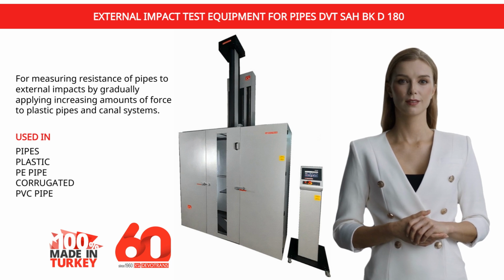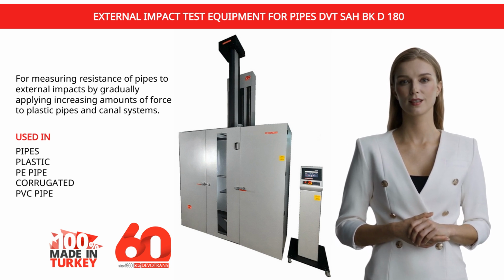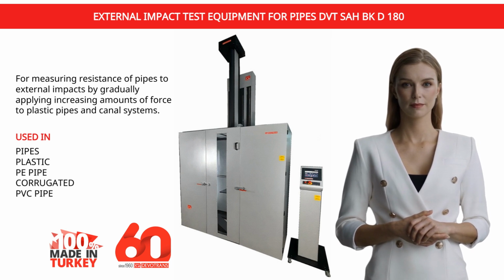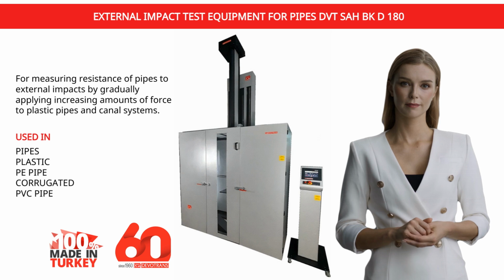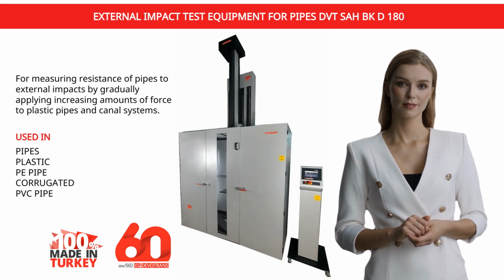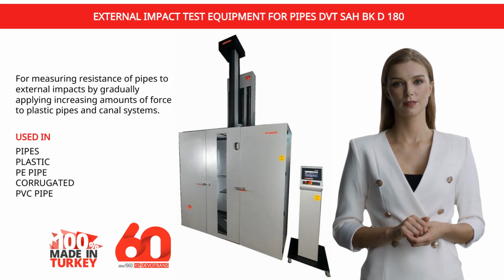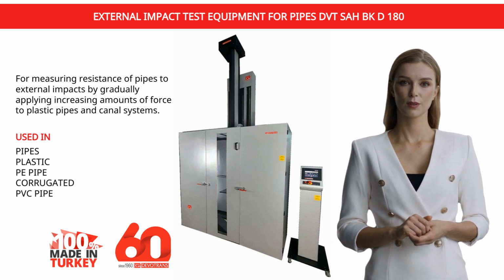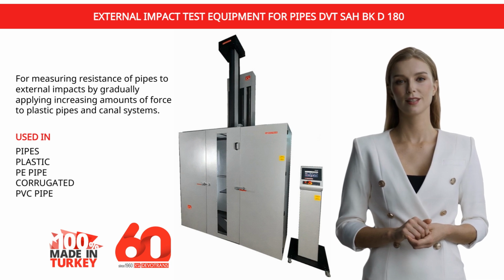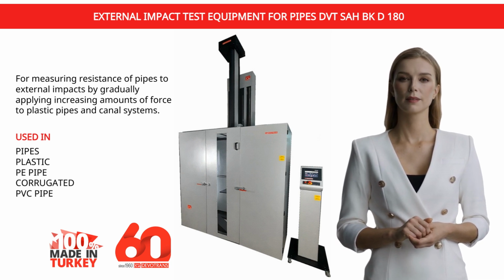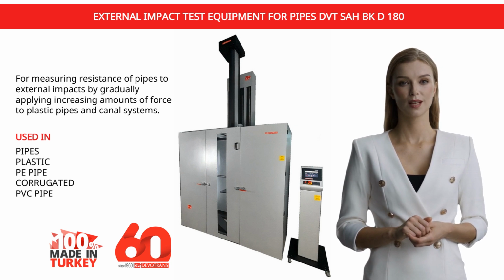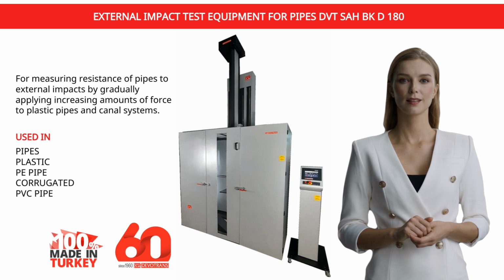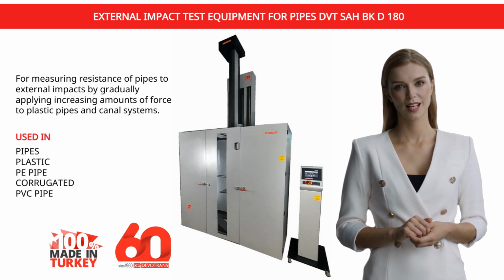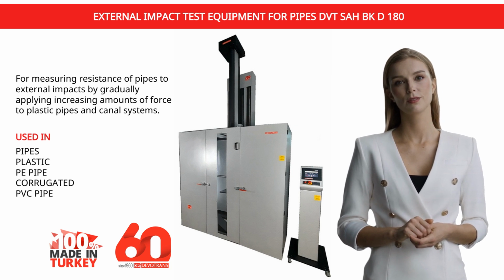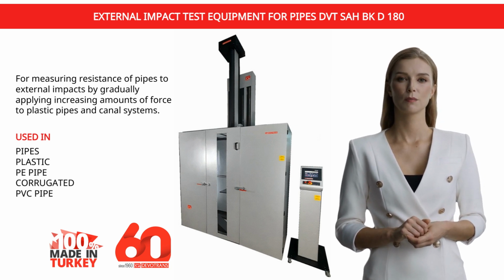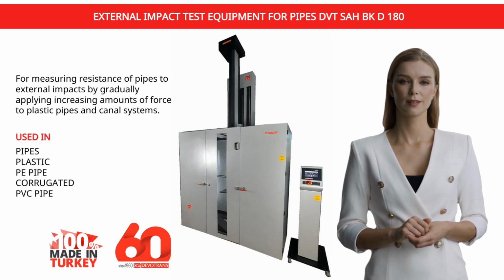1. Testing standards. The external impact test is conducted according to certain standards. Some commonly used standards include ISO 3127, Standard for Impact Testing of Plastic Pipes. ASTM D2444, Standard for Testing the Impact Resistance of Plastic and Metal Pipes. EN 744, Standard for Evaluating the Impact Resistance of Pipes and Fittings. These standards guide how the test should be conducted, the equipment to be used, and parameters like the impact weight and drop height.